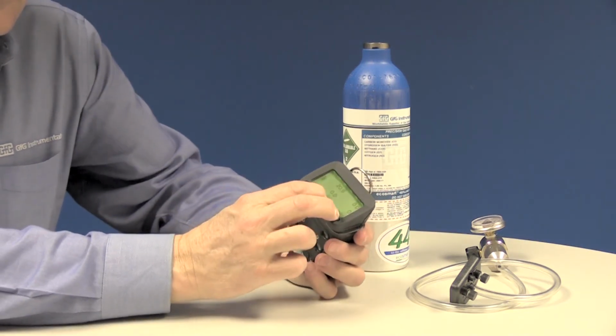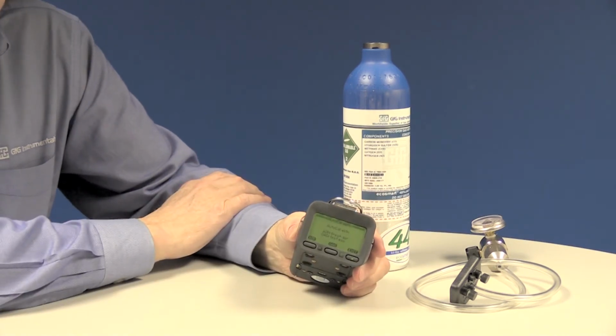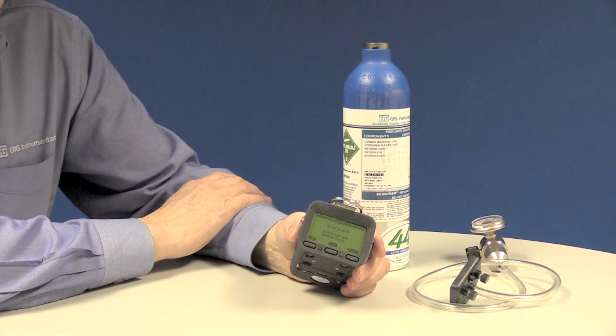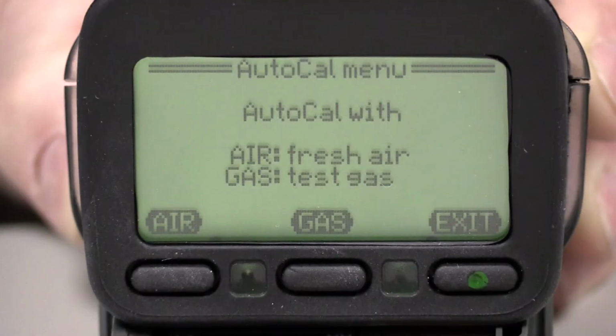Press the reset and zoom buttons at the same time to enter the autocal mode. Do not hold the buttons down, just press them once at the same time. The instrument will display the autocal screen. The screen gives you 3 choices. The left-hand air button is used to perform the automatic fresh air adjustment. The center gas button is used to adjust the sensors while they are exposed to gas. The exit button is used to leave the autocal mode and return to normal operation.